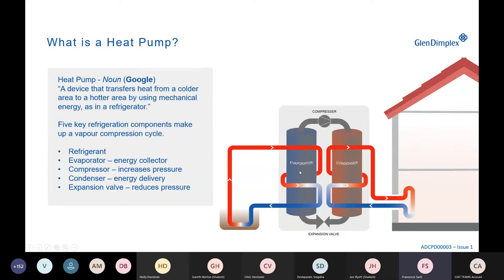After that, you compress the gas by means of a compressor, which reaches a higher temperature, and you use this higher temperature in the condenser, another heat exchanger, to heat up water. The second circuit is water going inside your dwelling or building. After this cycle is complete, the refrigerant is expanded in the expansion valve, goes back into the evaporator, and the cycle begins again.